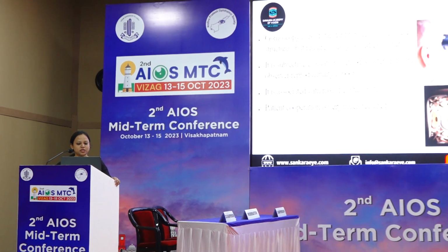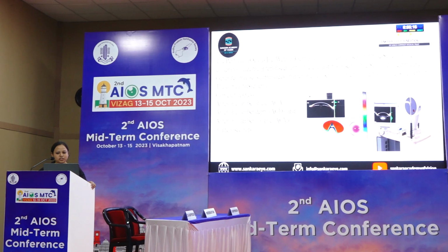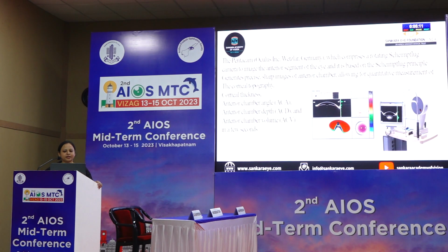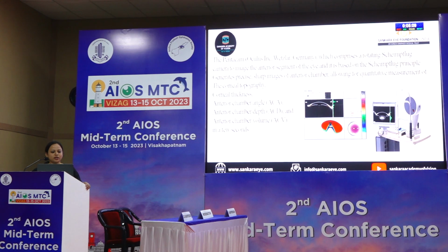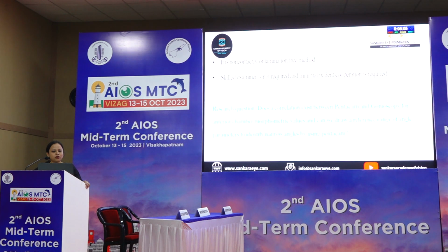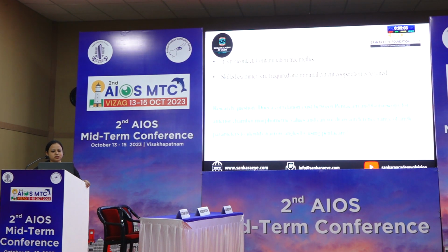Gonioscopy is the gold standard, but it is a subjective evaluation method, so intra-observer reproducibility is poor, it is associated with risk of contamination, and much patient cooperation is required. Pentacam is based on the Scheimpflug principle and generates precise, sharp images of the anterior chamber, allowing quantitative measurement of topography, thickness, and anterior chamber morphometric values in a few seconds. It is non-contact, contamination-free, no skilled examiner is required, and minimal patient cooperation is required.